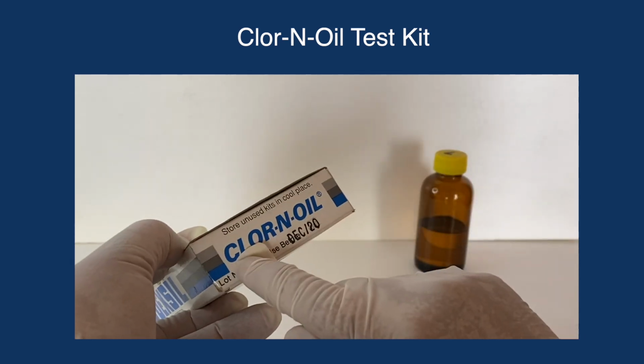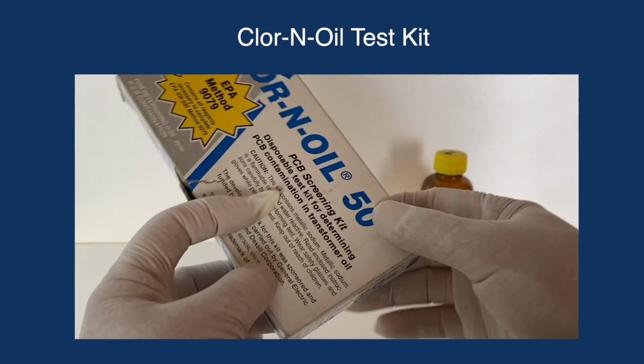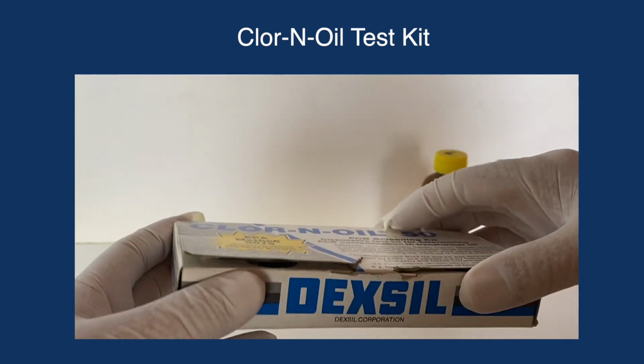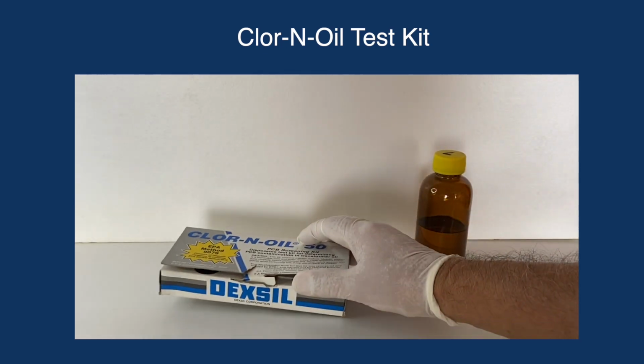The Clor-N-Oil test kit is a disposable all-inclusive test kit specifically developed for the determination of PCB in transformer oils. For the PCB inventory, the test kit with the action level of 50 parts per million should be chosen. The test kit is calibrated on Aroclor 1242, the Aroclor with the least amount of chlorine, 42% by weight, to obtain the most conservative results.